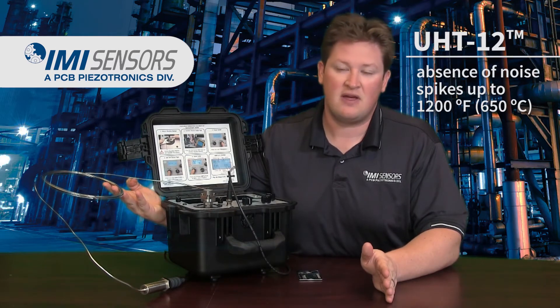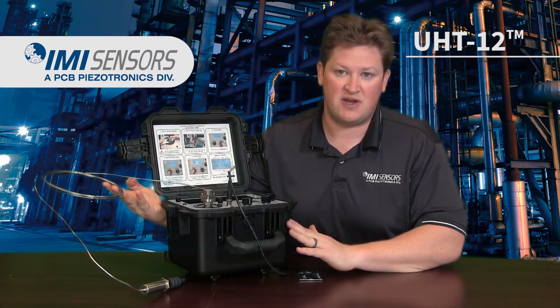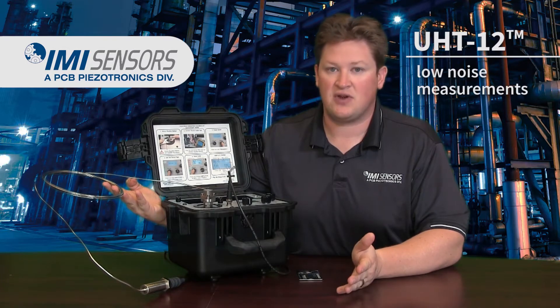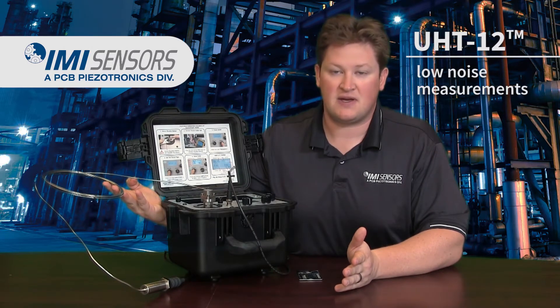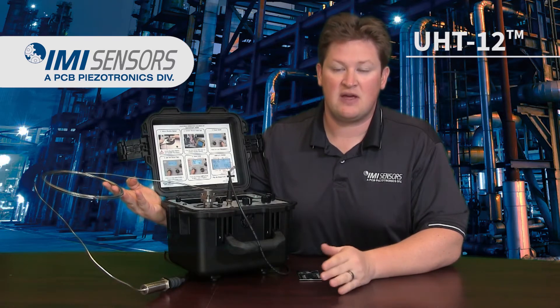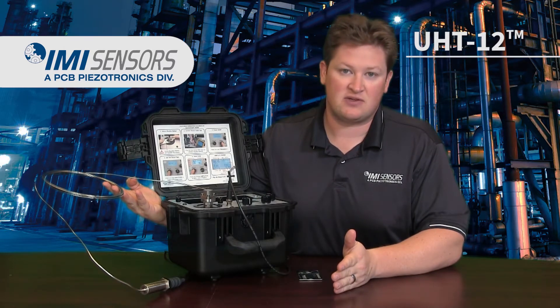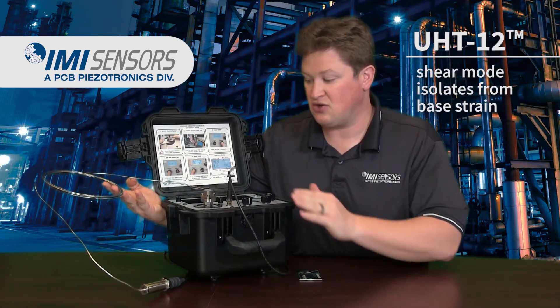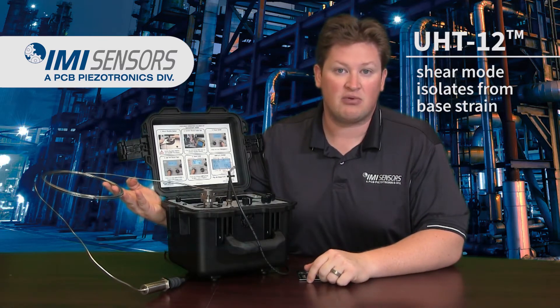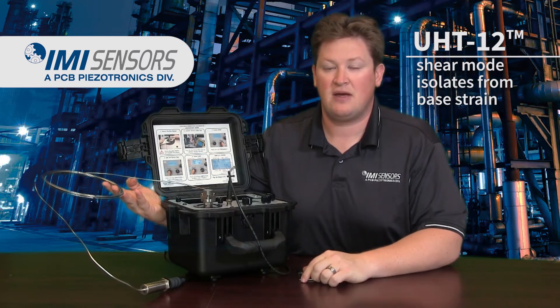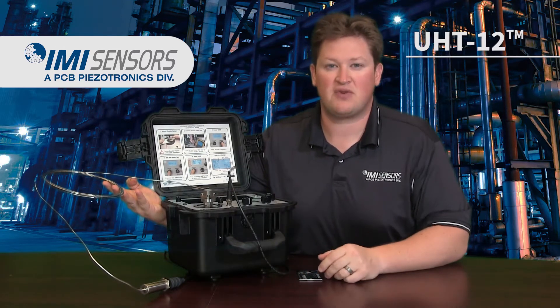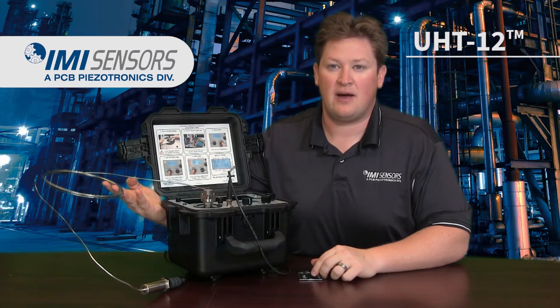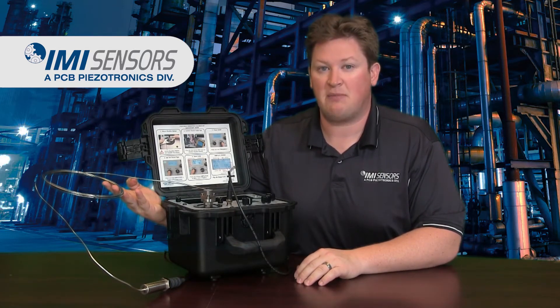This unique crystal design, trademarked by PCB Piezotronics, is excellent at removing those noise spikes as well as giving terrific temperature stability. And finally, it has a shear mode element instead of a compression mode element, which prevents base strain errors due to the base strain that may be induced by the strain on the sensor's mounting by the motion of the machine itself or the flexing of the machine itself. It's a huge step up in the high temperature sensor design world.